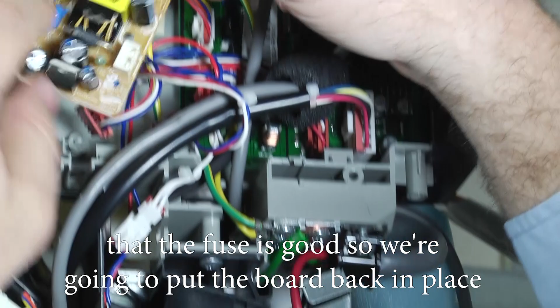One thing I do want to show you, if you look closely at this board, there's a box that says DC link. Number 1, 2 is NC (not used), 3 is NC (not used), number 4 is 17 to 25 volts, and number 5 is ground. Those are the pins here in this plug: here's 1, two blank spaces, then 4 and 5.